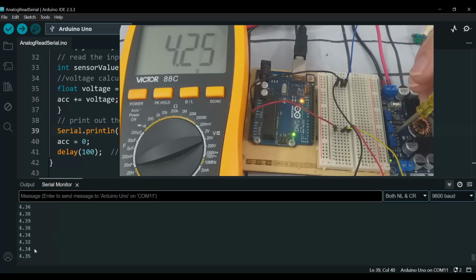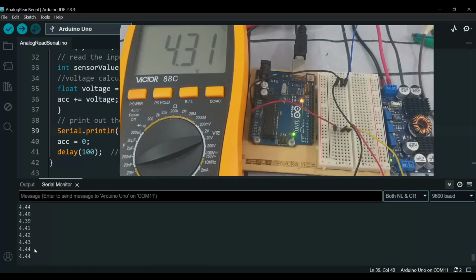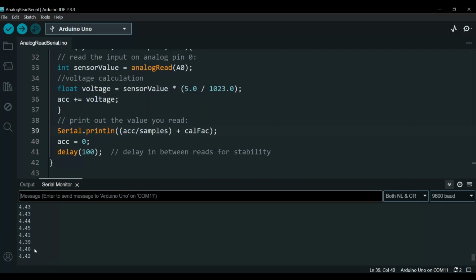If I go all the way, let's say to 4.2, here we go, for 4.25 we get 4.3, which is 0.05 different, looks okay also. Now if I go to 4.8, the reading is about 5 volt. Now we can see about 0.14 different, with 100 millivolt, but it looks okay. Okay, that's good. So this is how we can implement the single point calibration. For sure, you can't expect very high accuracy from a single point. Otherwise, we need to go for 2 point calibration, and this is what we will discuss next.